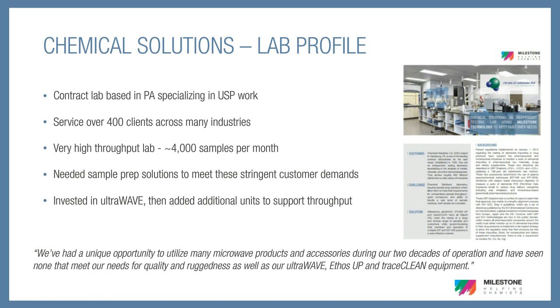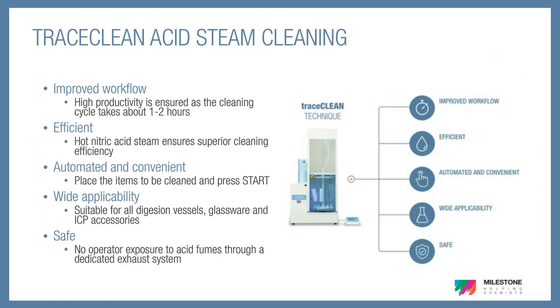For those of you not familiar with it, the Trace Clean is an acid steam cleaning system by Milestone, which automates the cleaning of any sample prep components compatible with acid, from vials to ICP torches. The system is fully automated and takes about one to two hours for the cleaning cycle to complete. Following cleaning, components are cool and dry and can be stored in the system's clean environment until needed. By using the Trace Clean, you can eliminate the need to clean vessels in your microwave, or even use it instead of an acid bath or other less efficient cleaning techniques.